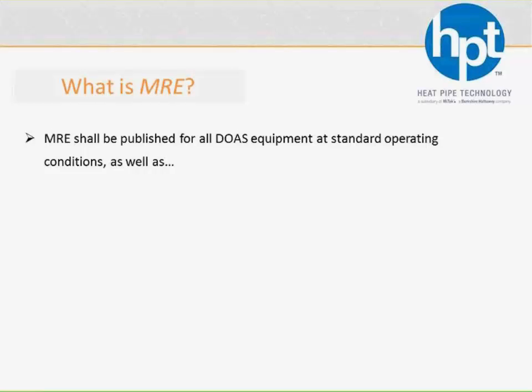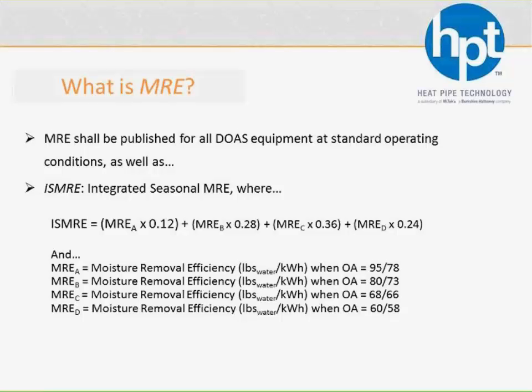So MRE is not just now standardized by 920, but 90.1 is going to set up some minimum tables that all DOAS manufacturers are going to have to comply with, and all DOAS manufacturers are going to have to start publishing their MRE at standard operating conditions, which I'll show you. But not just MRE, there's another term called ISMRE, or the Integrated Seasonal MRE, which is very similar to the NPLV of a chiller. If MRE is at full load, ISMRE is measuring the part load performance. So it's a weighted MRE looking at various conditions, and you can see them below, conditions A through D, where A is full load at 95, 78, all the way down to 60 degrees, and it weights those and tells you what your average MRE is going to be based on standard operating conditions.